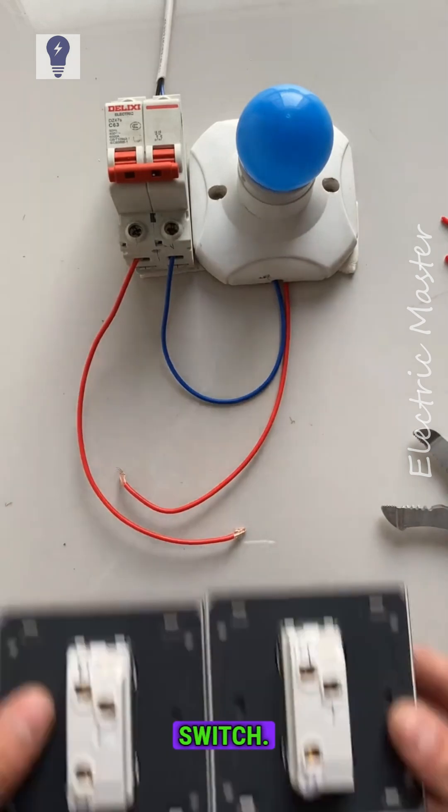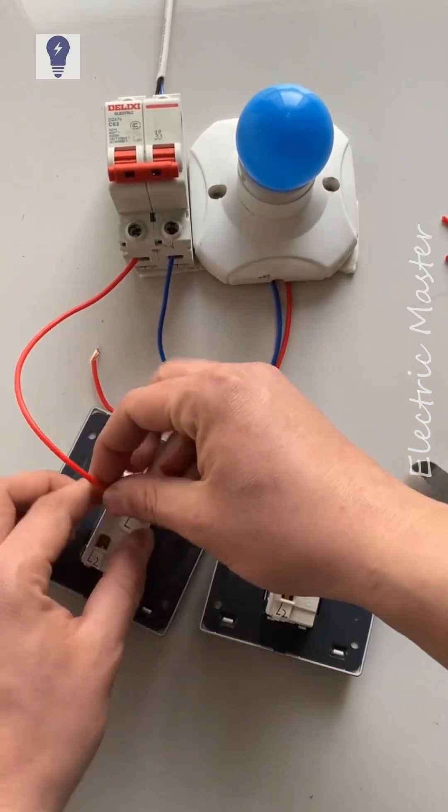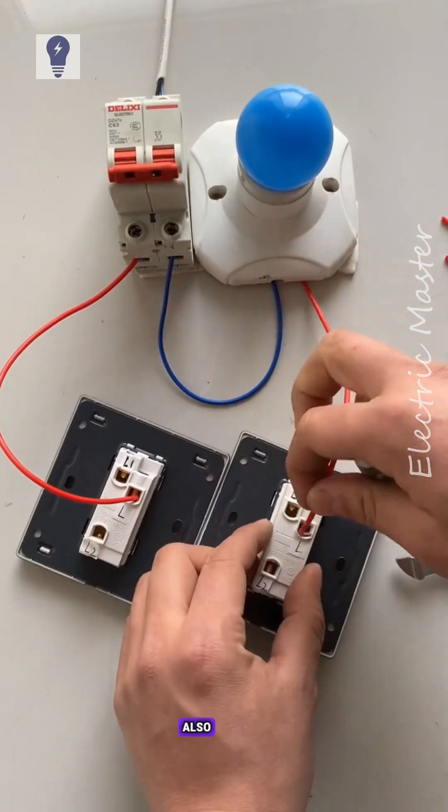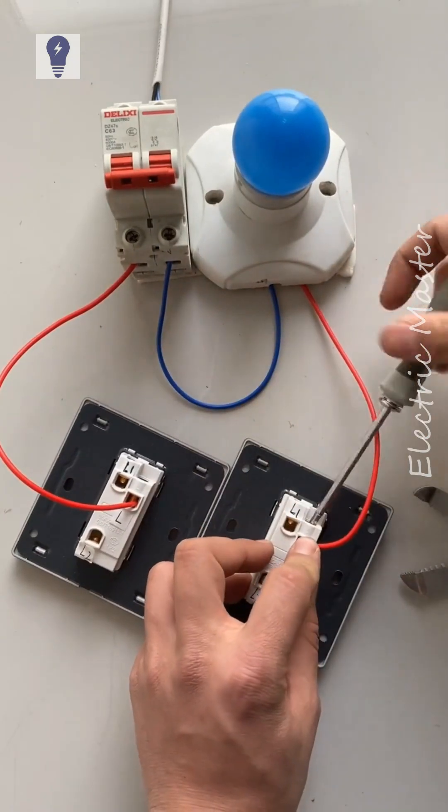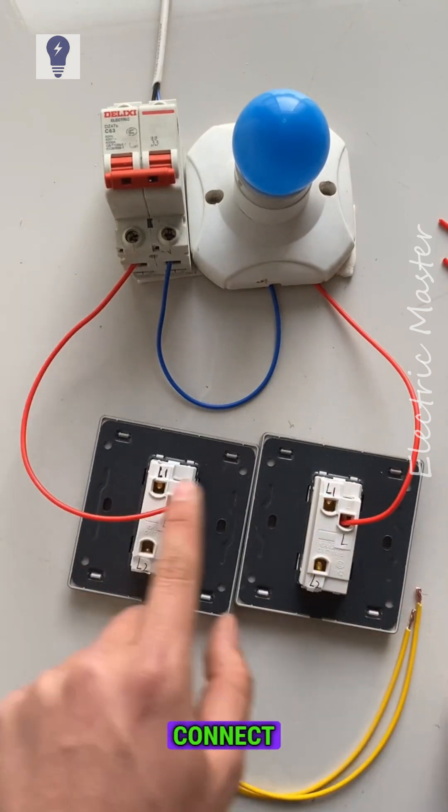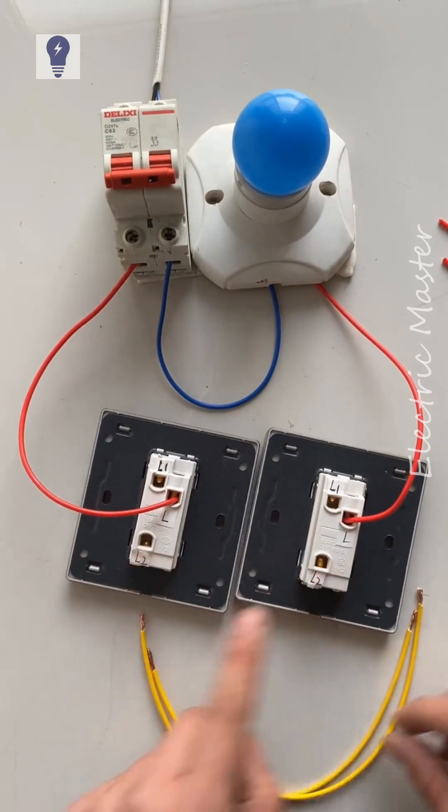This is a single pole switch. Prepare two single pole, dual control switches. Connect the live wire to L. Also connect the control wire to L. Now, let's find two more wires. Connect L1 to L1 and L2 to L2.